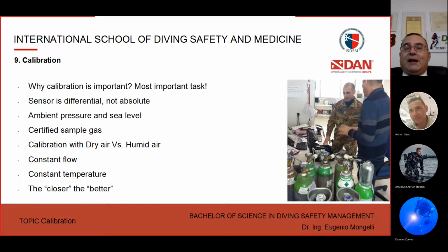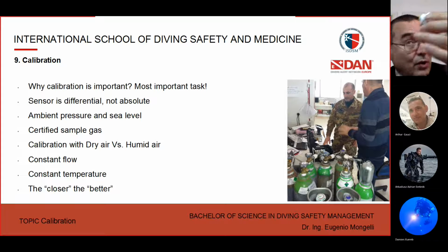Okay, why is calibration so important? Simply because the sensors are differential, not absolute. I mean, when you have this sensor, this is the typical oxygen sensor, it gives you just a millivolt output, a voltage tension.